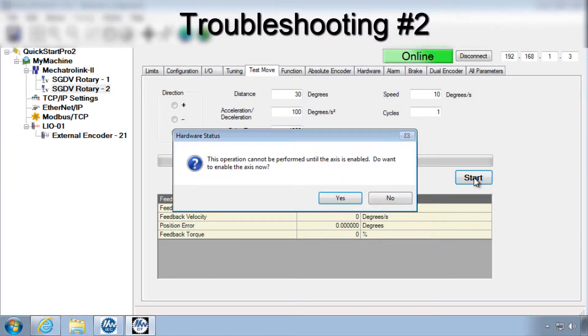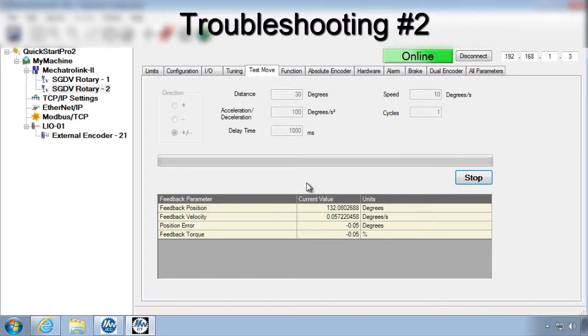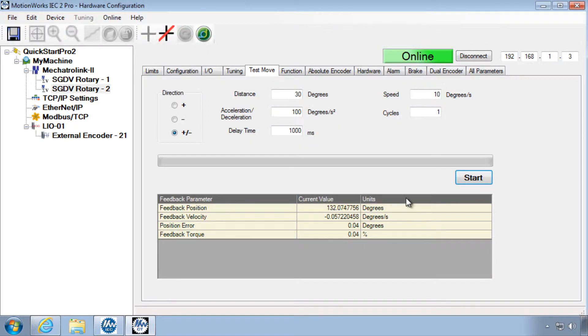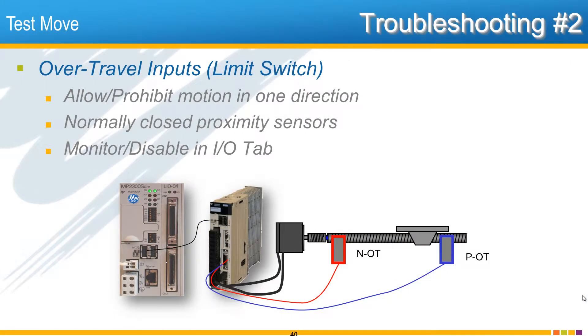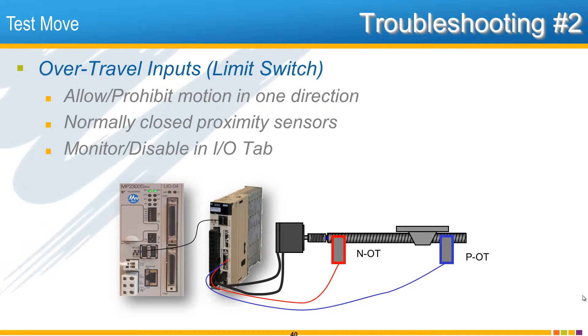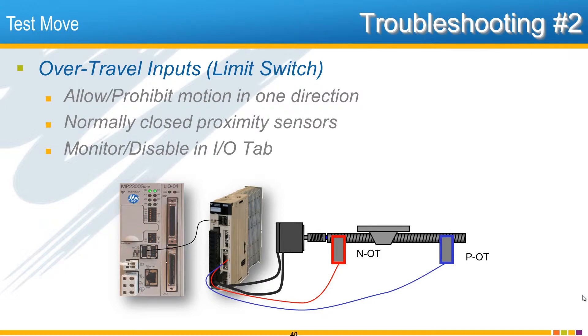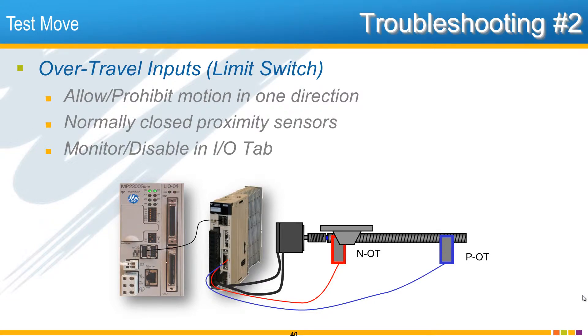If when you click start the axis enables but just doesn't move, the most likely cause is the over-travel condition, otherwise known as limit switches. Over-travel is not an alarm, but they are digital inputs that allow or prohibit positive and negative motion. The over-travel inputs by default are to be connected to normally closed proximity sensors at the end of a linear actuator in order to stop that load from reaching the mechanical limit.